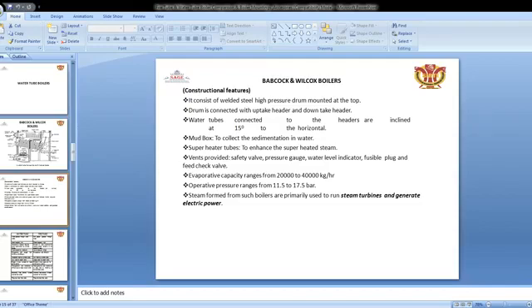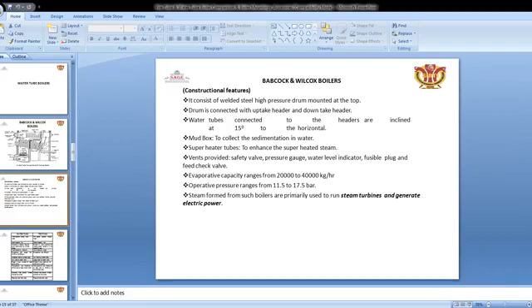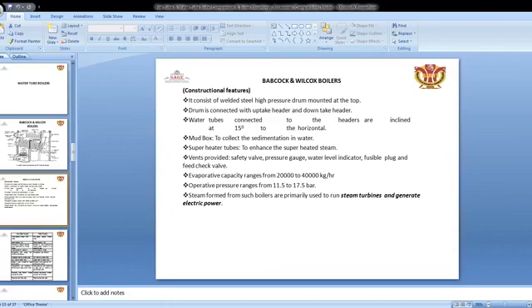The Babcock and Wilcox boiler consists of a welded steel high-pressure drum mounted at the top, connected with the uptake header and downtake header. Water tubes connected to the headers are inclined at 15 degrees. A mud box collects sediments in the water. Superheater tubes enhance the superheated steam. Fittings provided include safety valve, pressure gauge, water level indicator, fusible plug, and feed check valve. Evaporative capacity ranges from 20,000 to 40,000 kg per hour. Operating pressure ranges from 11.5 to 17.5 bar.